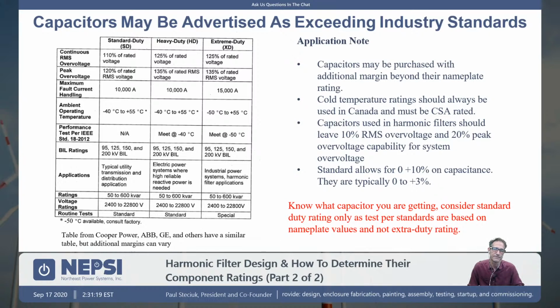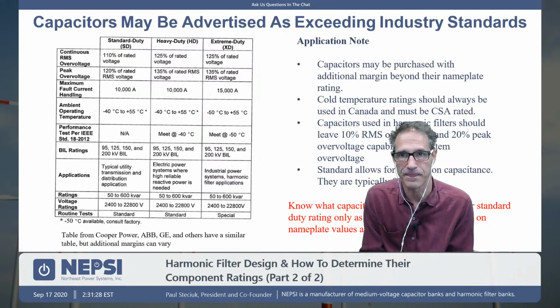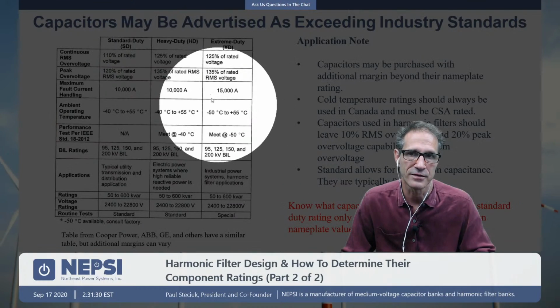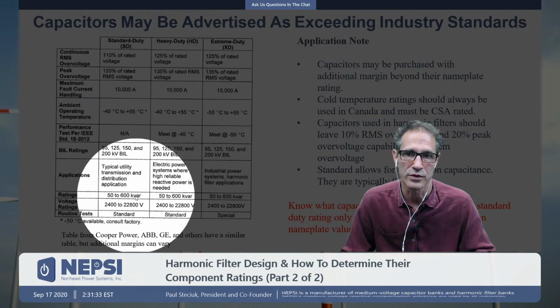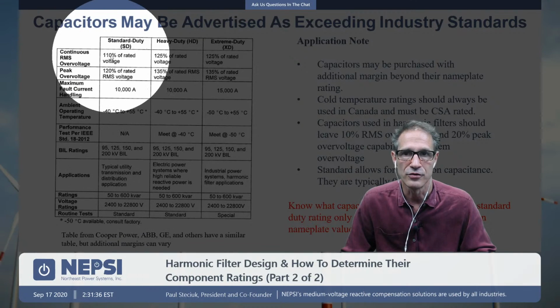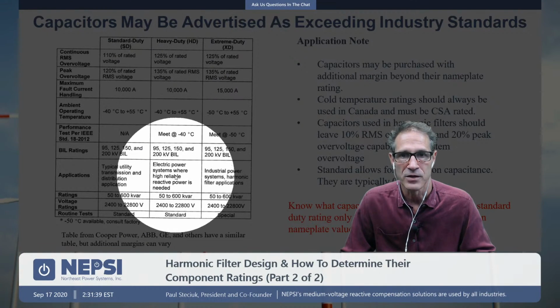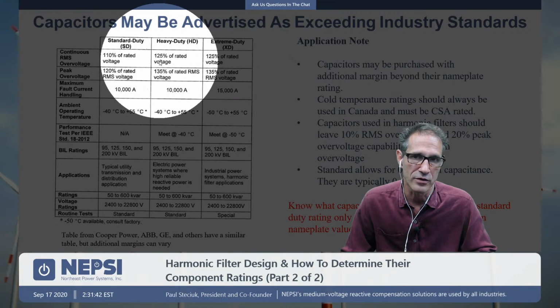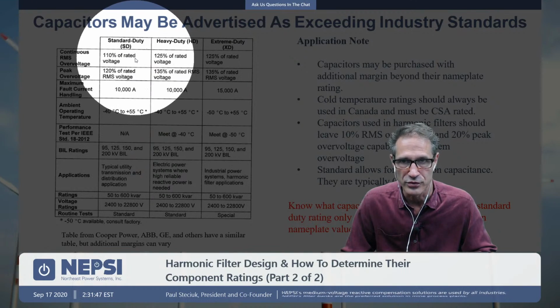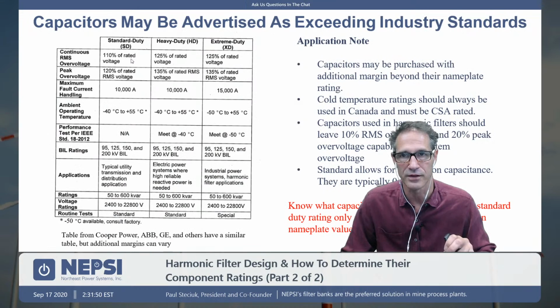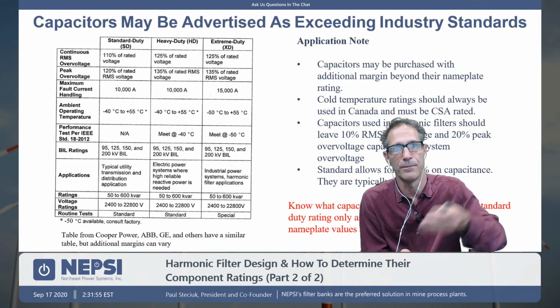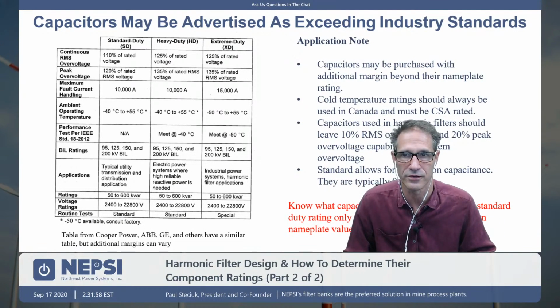The key that you want to be careful about is that when a capacitor manufacturer tests the capacitor on its assembly line, they're basically testing against the standard duty value, the base value, what the standards require. So you can ask for a heavy duty design, but it doesn't mean that the capacitor came off the assembly line and was tested at 125%. So if you really want to make sure that you're getting a capacitor that carries its actual rating, you want to buy standard duty rated capacitors and bump up the voltage. Okay, so this is one thing to think about.